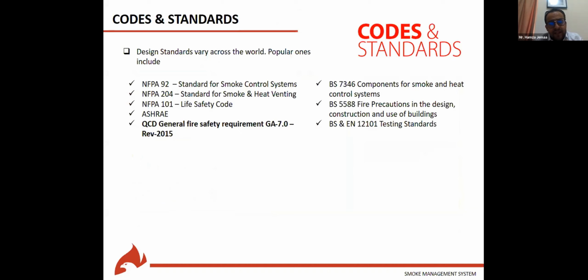Here an idea about the codes and standard used in the smoke control to design and maintain smoke control system. The first, NFPA 92, is for smoke control system. NFPA 204 is for smoke vent design and mechanical installation maintenance. NFPA 101, ASHRAE handbooks, and QCD, General Fire Safety Requirement, the guidelines, Annex 7.0, Revision 2, 2015. Also, BS and EN standard are used for the testing of the product, and mainly European products are all following the EN 12101 standard.